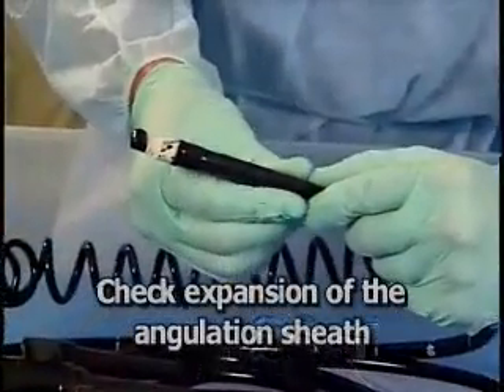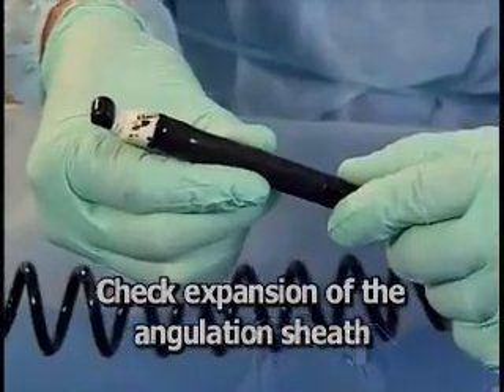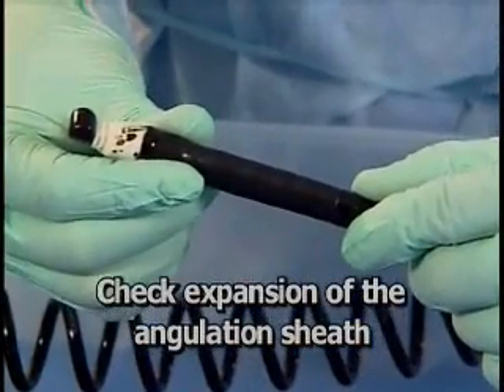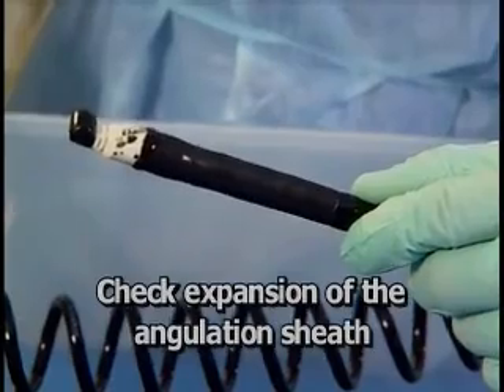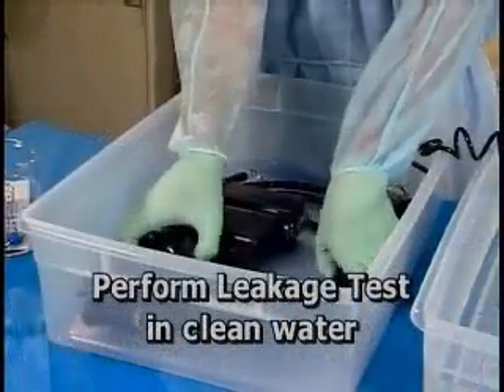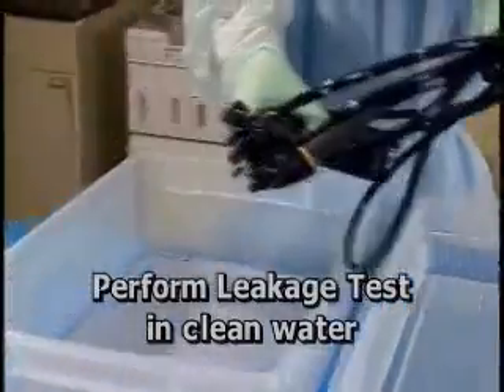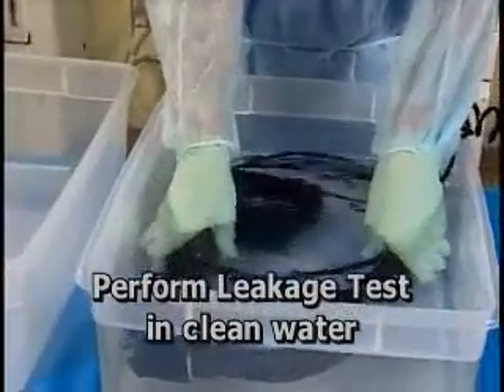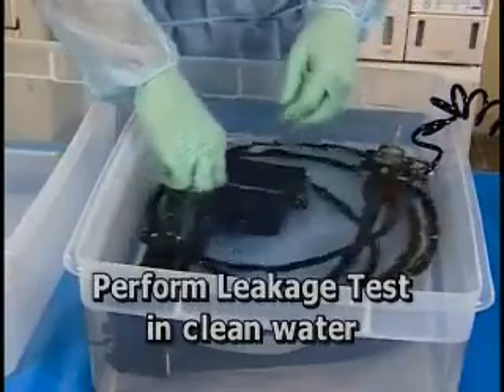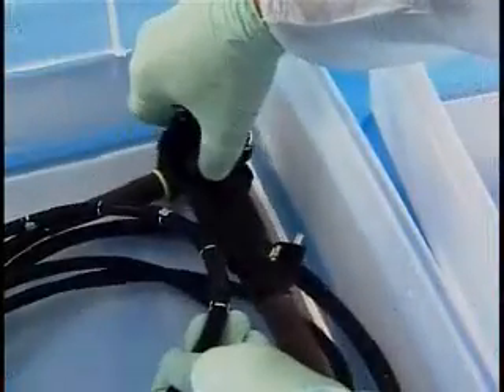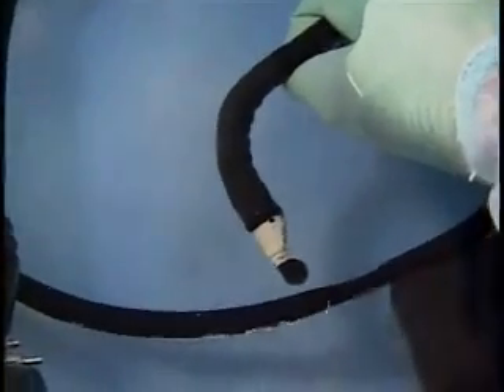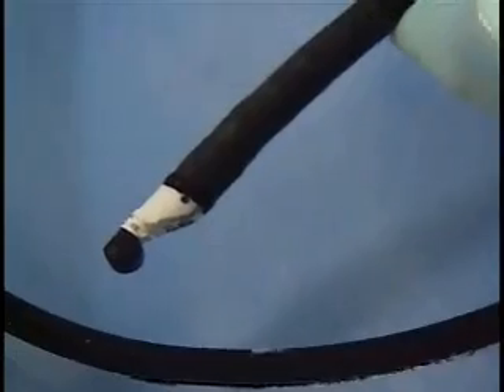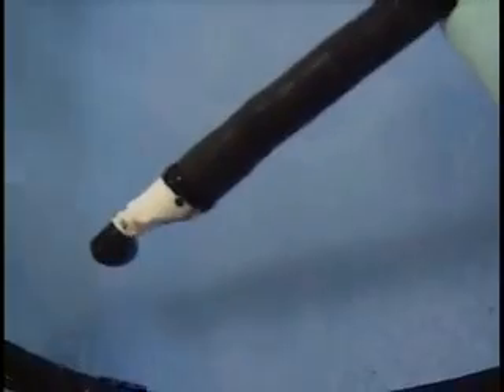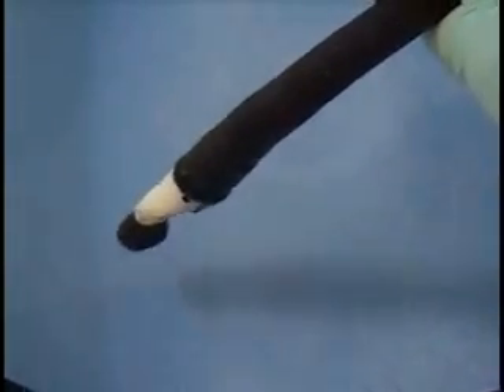Note that as you pressurize the inside of the endoscope, the sheath on the distal tip of the endoscope will expand. Now, immerse the endoscope in clean water. Do not leak test in detergent, as detergent will hinder visualization of leaks. With the angulation locks in the free position, angulate the endoscope tip in all directions. Deflecting the tip will help expose any pinholes that may exist in the bending section.